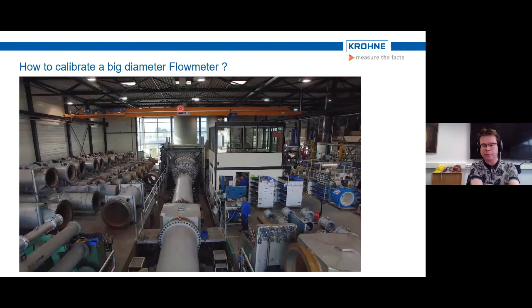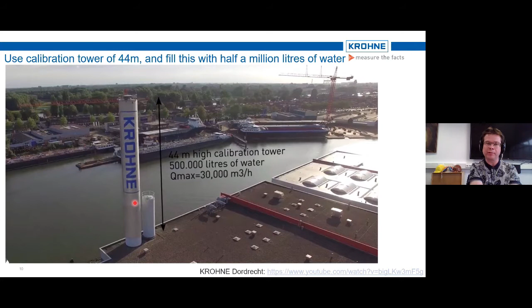But how do you calibrate a big flow meter? You need a really big amount of water pumped through the meter. In our production facility there's a really big pipe that goes up to the roof, leading to a calibration tower 44 meters high, which can contain 500,000 liters of water. Once you want to calibrate a big flow meter, you open the valve—you know how much water is inside the tower—it goes through the roof and through the flow meter, and at the end you can calibrate even the really big flow meters.